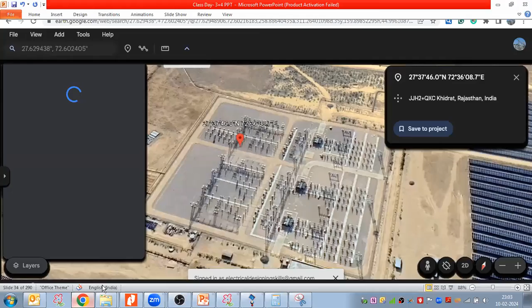Where the site land is expensive but less available, the GIS type substation is mostly used. Where the pollution level is very high, or where the site temperature is very much high, GIS type substation is preferred over AIS substations.